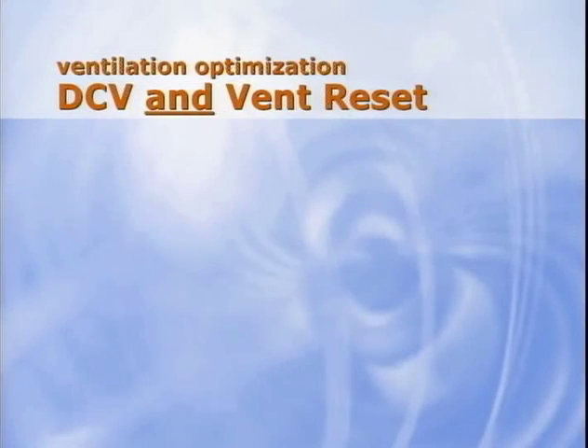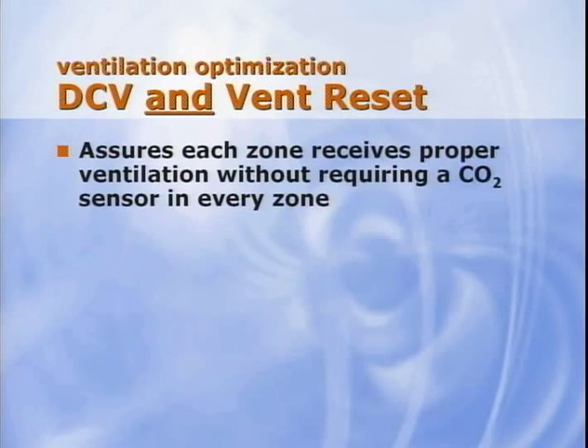Combining demand control ventilation at the zone level with ventilation reset at the system level has the following benefits. It can ensure that each zone receives the proper amount of ventilation without requiring a CO2 sensor in every zone. CO2 sensors are used only in those zones where they will bring the most benefit. This minimizes installed costs and avoids the periodic calibration and cleaning required to assure proper sensor operation. For the other zones, occupancy sensors and time-of-day schedules are used to reduce ventilation.